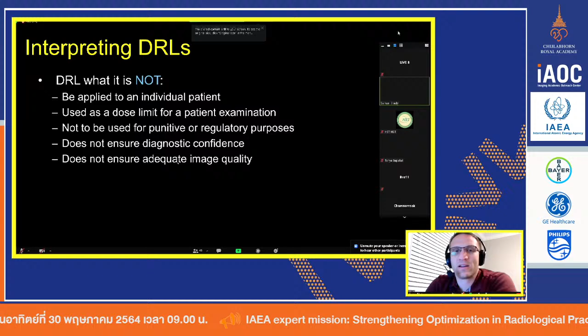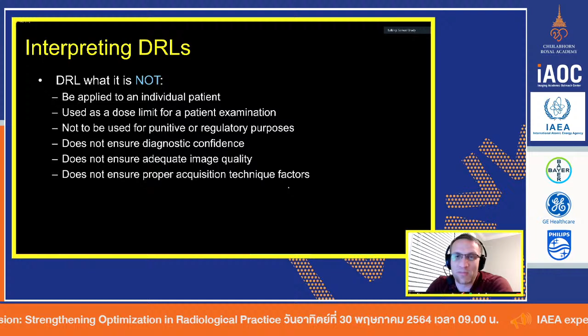Yes, and it doesn't ensure proper acquisition technique factors. So you might actually be getting a dose that's lower than that, but you might be using the wrong kV for whatever reason. Maybe you got your kV set too low. So the dose might be low, but the image quality might not be so great.